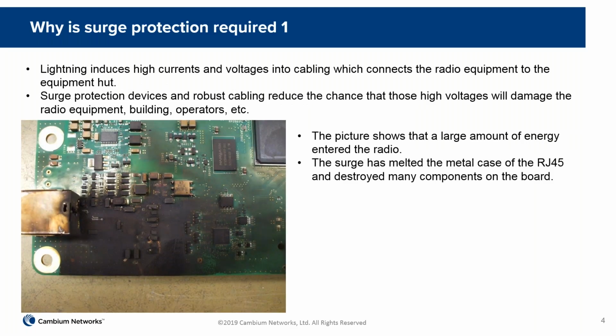So why do we need surge protection? Here's a board which obviously has suffered some damage. There's a lot of damage: smoke damage, and within the metal case of the RJ45 we can see that the energy has been sufficient to actually burn holes in it. So there is a lot of energy that has to be absorbed, that has to go somewhere during a surge event.